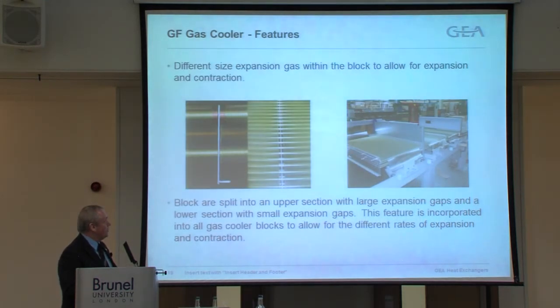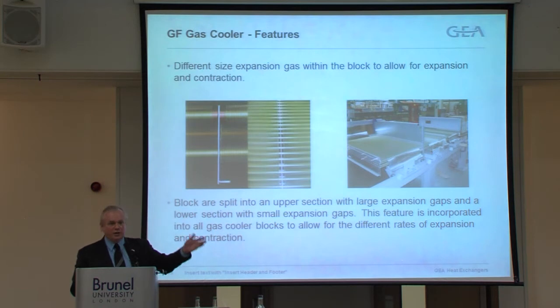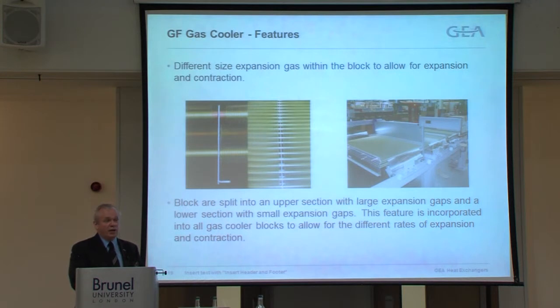Simon talked briefly about the coil being split from the top to the bottom. We have got a lot of experience on steam coils and engine cooling where we're operating at 100, 110 degrees C. And the biggest problem that we've actually found is that when you're making something that's 7 or 8 metres long, the expansion and contraction that you get on the matrix is tremendous. So we have the split coil, effectively a de-superheater, I suppose, then going into the gas cooler. They're completely separate. The tubes are separate, the fins are separate, and this is to allow for the different expansion and contraction rate that you get on the top of the coil versus the bottom of the coil.